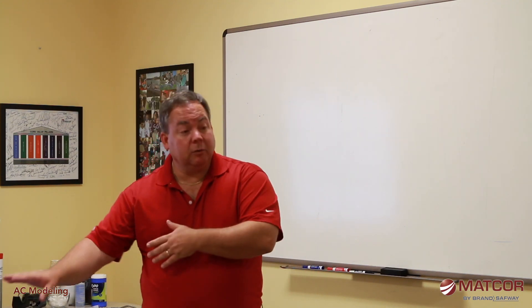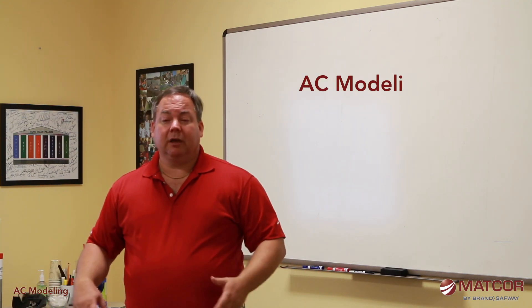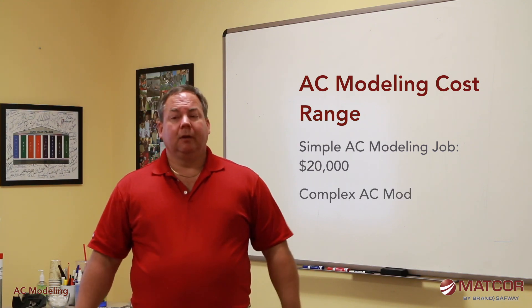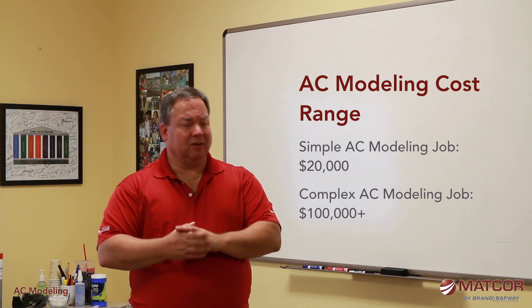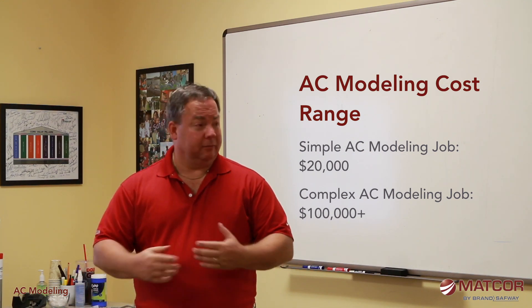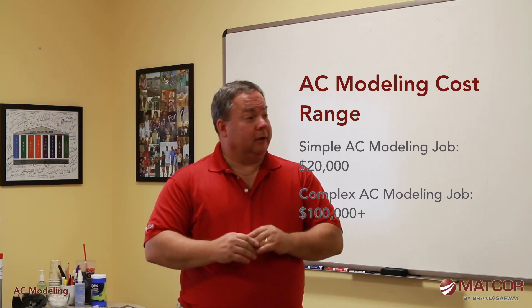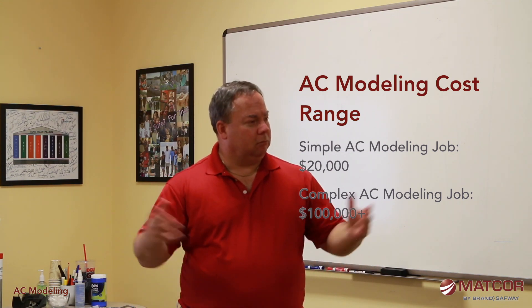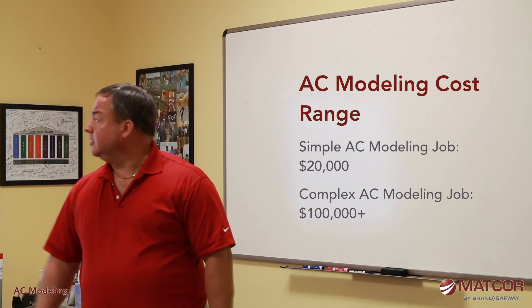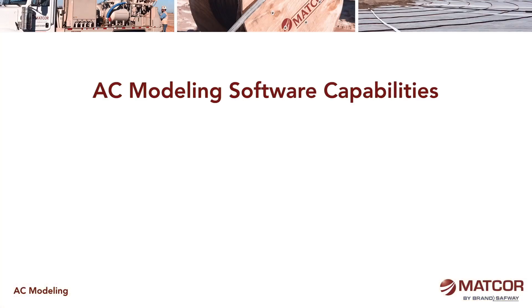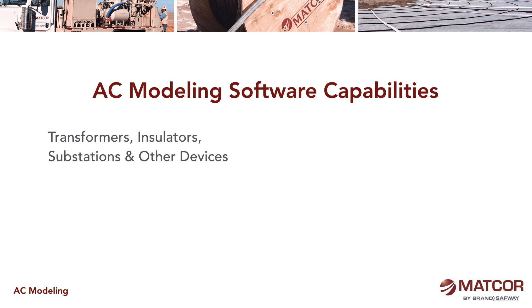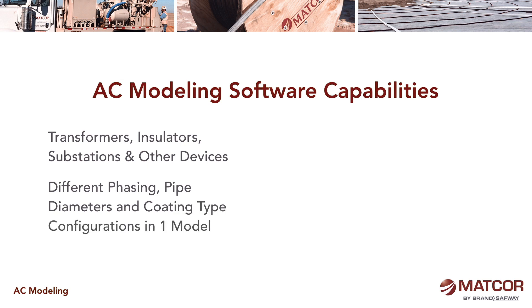For a relatively simple co-location, you may not need full modeling. Modeling typically costs anywhere from $20,000 for a simple job to well over $100,000 for a large job due to extensive data collection and modeling effort. In some cases it may be simpler to just put $10,000 worth of grounding in and over-design the solution, because it's not worth spending $20,000 on a model. In other cases, modeling is an absolute necessity.